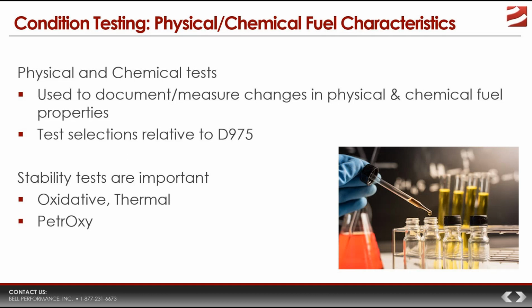So despite being predictive, stability tests have a lot of value because they can allude to present-day things like microbial contamination that might be present in the stored fuel and might have contributed to that score being less than what we would expect it to be. If something has happened to the fuel while in storage, like development of significant microbial presence, then typically there will be other things that happen along with it, like the development of unstable precursor molecules that, if you give them enough time, will cause changes in the fuel.